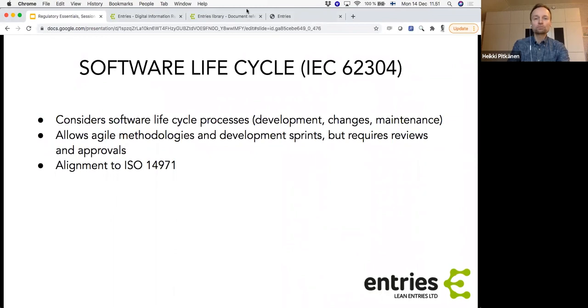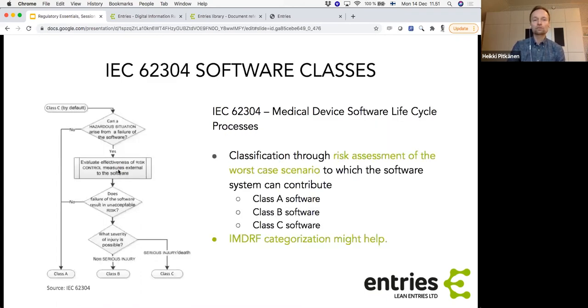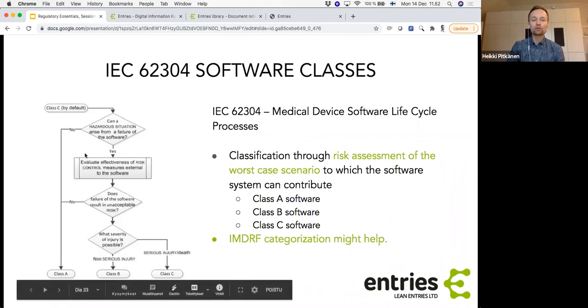Then let's talk about that software. The software lifecycle standard, IEC 62304, contains all processes within the lifecycle: development, changes, and maintenance. It leaves room for agile methods, and you can, by all means, have your development sprints, but you need to apply the relevant reviews and approvals. And this again aligns with ISO 14971 and talks a lot about risks. And now we get to the point where we had that software risk class in the table as well. The standard defines that you must develop your processes within your quality management system to develop and maintain the software depending on the level of severity it provides for the user.